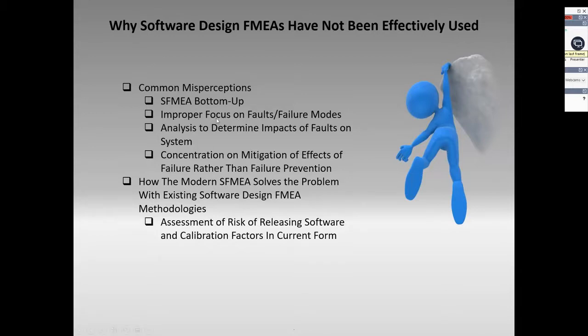As I talked before, there was a focus on determining all the different ways your software can fail. No. What you have to do is determine what the requirements are you have to meet. You have to define the code that controls meeting those requirements, and you've got to prove that code is correct through your design verification. Again, this concentration on mitigation of effects, no—we're going to concentrate on getting the code right.